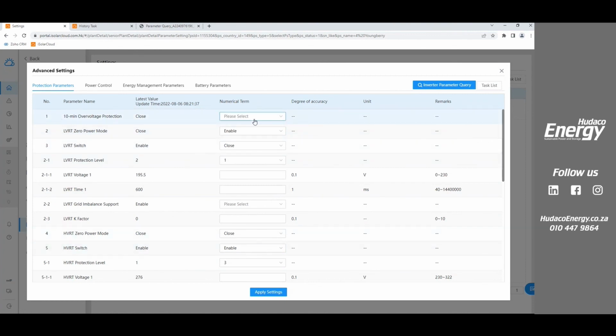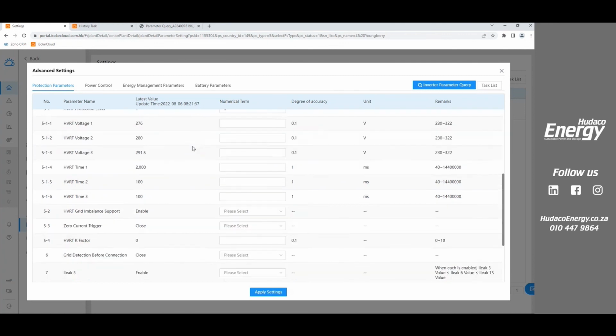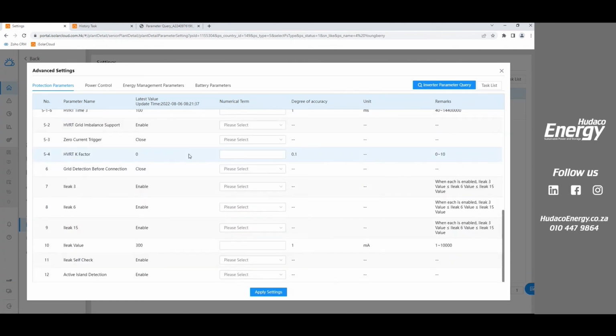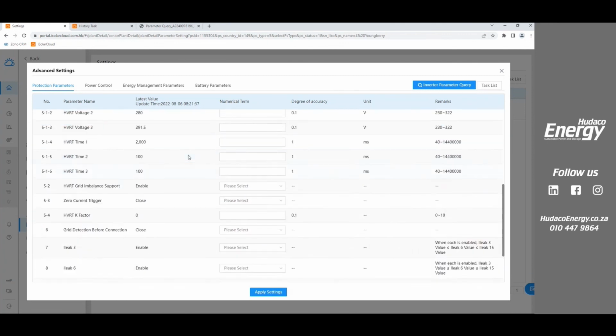This 10-minute over voltage protection, please be careful of this, because if you enable this, the moment it detects that, it's going to shut down, and it's not going to recover when your voltage restores. It's going to wait for 10 minutes before it even starts checking again. I hope I'm not confusing or losing anybody on this. Normally we'll cover these things under more of the advanced settings.